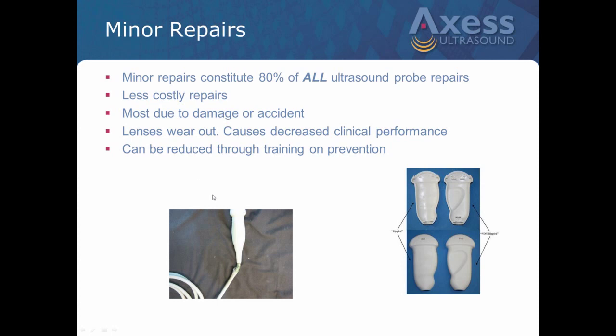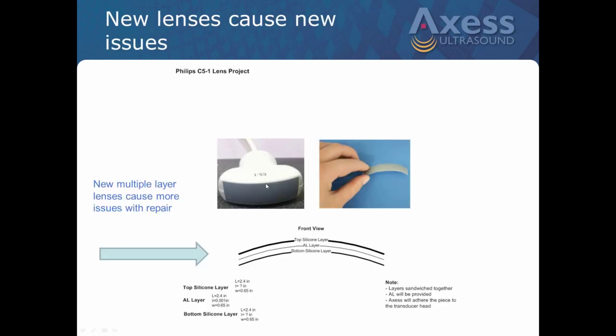And the aluminum acts as a filter, and it filters out a lot of the noise and so on in the probe. Now, what we've seen is that these things pop up. They're adhered to the array stack here inside the C5-1. Here's what an OEM one kind of looks like. But it's critical that if you have to replace this lens, you do it right. In the next couple of slides, I'm going to show you why.